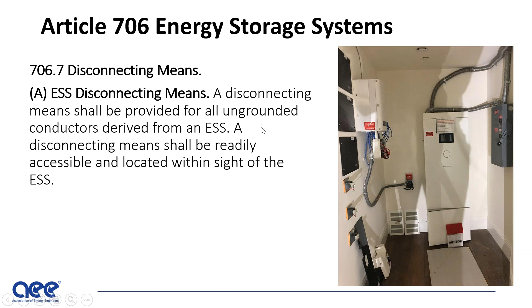There's also the opportunity to do remote disconnecting. If you look to the far right, you'll see this fusible disconnect or safety switch. It's off there, but it could be in the on position as well. That's disconnecting the power. You also have the ability to use remote actuation, which would be an e-stop type button that, when you hit it, trips the automatic disconnecting means. If you had a contactor or a breaker, you could shunt trip it.